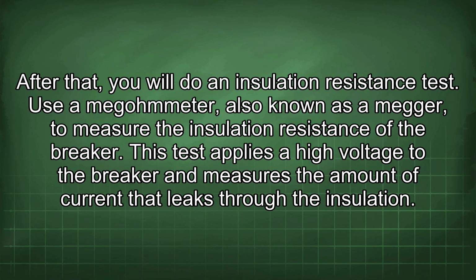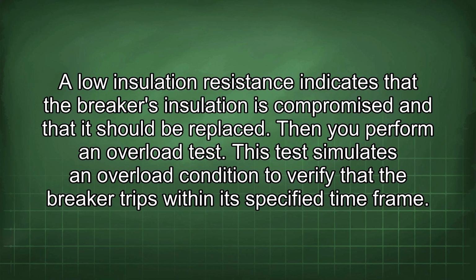After that, you will do an insulation resistance test. Use a megohmmeter, also known as a megger, to measure the insulation resistance of the breaker. This test applies a high voltage to the breaker and measures the amount of current that leaks through the insulation. A low insulation resistance indicates that the breaker's insulation is compromised and that it should be replaced.